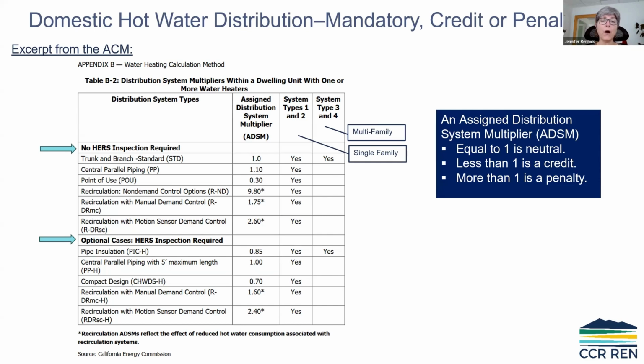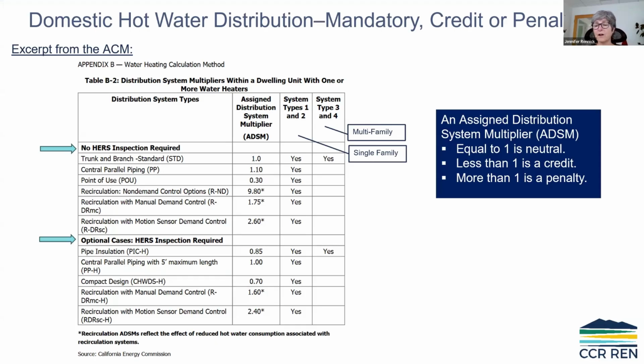But that's okay because you were already pulling cold water from the city or from your well into your tank anyway. So this is just less cold water adding to it, and it doesn't waste water while the hot water makes its way to that fixture. We're seeing more of those, but that type doesn't really fall into these categories with the really big penalties, because it's not causing your water to just recirculate willy-nilly, or recirculate because you press a button and now all of your fixtures and the water everywhere is recirculating.